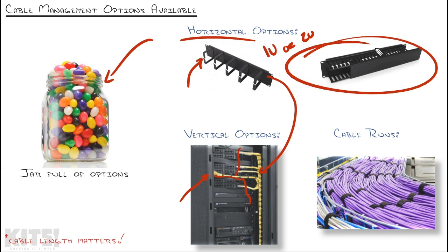That's why I usually go for one of these types of slotted duct cable management. You can see all of these teeth that look almost like little combs coming out of it. You would take your cable and run it in from the side and then fish it out those individual combs to whatever devices they need to go to. There's also holes in the back where you can fish cable in from the back of the rack into the middle and then out the comb.